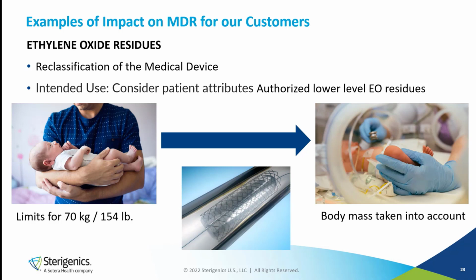So we know that with MDR, we have a higher focus on safety. We have a standard to define the level of residue required after an EO process. We had some data to support, for example, here stent, the EO residue level for an adult, but not always for babies. And we had to prove that the stent that could be used for both could achieve the right residue limits for both. So we had to perform additional studies to ensure that we have the right limits.